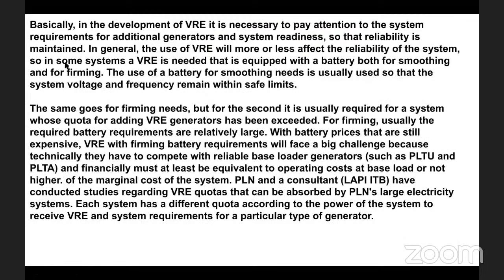require large capacity. Basically, in the development of VRE, it is necessary to pay attention to the system requirements for additional generators and system readiness so that reliability is maintained. In general, the use of VRE will more or less affect the reliability of the system. So in some systems, a VRE is needed that is equipped with a battery both for smoothing and for firming. The use of the battery for smoothing is usually so that the system voltage and frequency remain within safe limits. The same goes for firming needs, but the latter is usually required for systems whose quota for adding VRE generators has been exceeded.